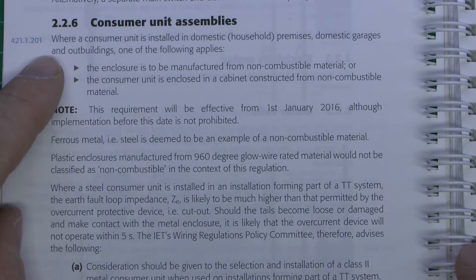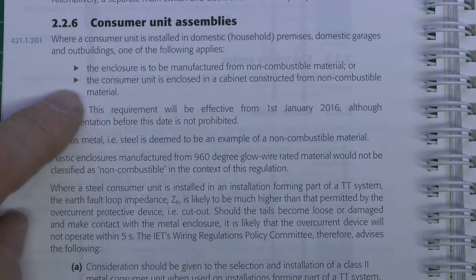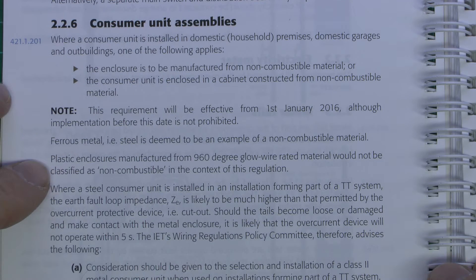It's where a consumer unit is installed in domestic premises, domestic garages and outbuildings, one of the following applies: the enclosure is to be manufactured from a non-combustible material, or the consumer unit is enclosed in a cabinet constructed from a non-combustible material. That's in effect from January next year, though you can comply before then. Ferrous metal, as in steel, is the example. Importantly, plastic enclosures manufactured from 960 degree glow wire rated material would not be classified as non-combustible in the context of this regulation.